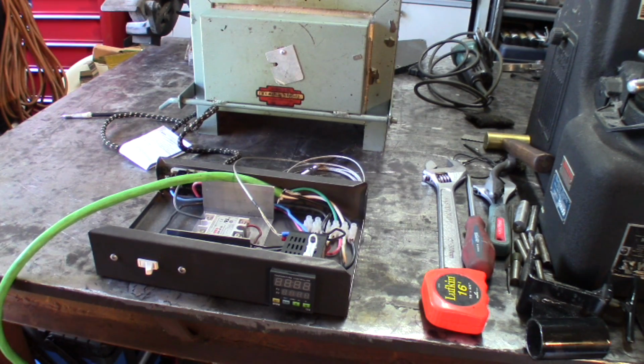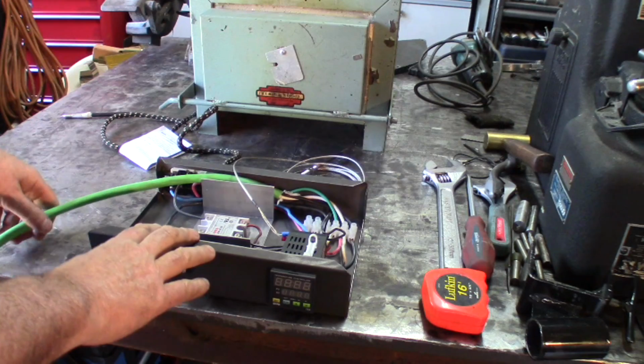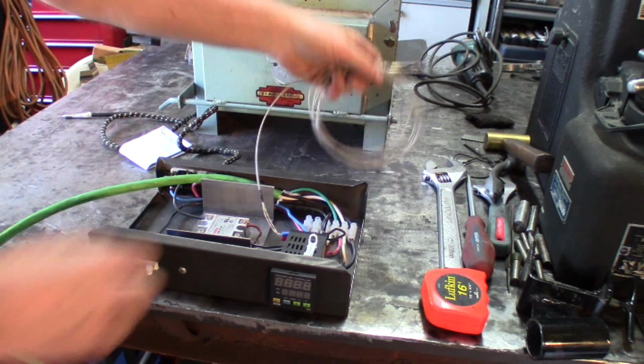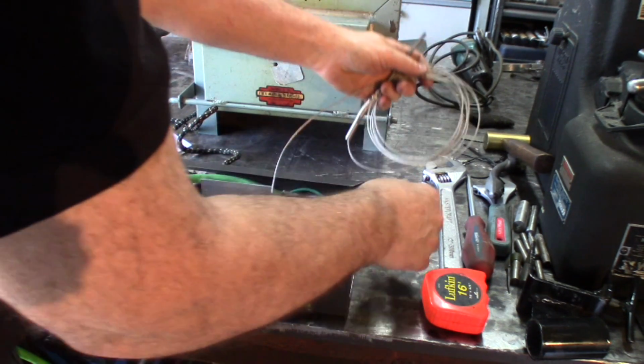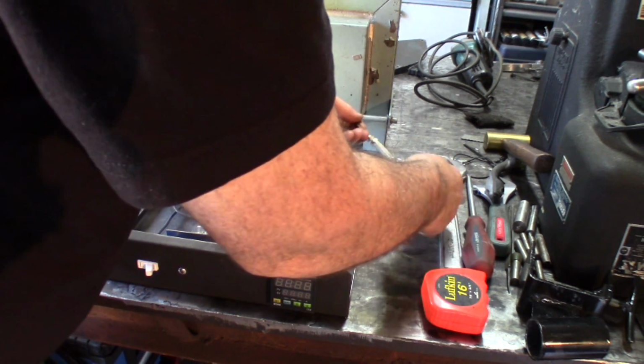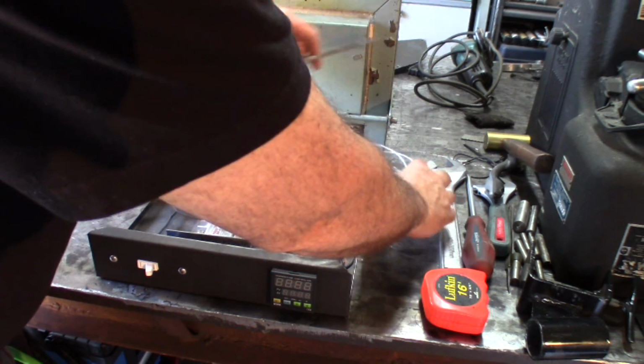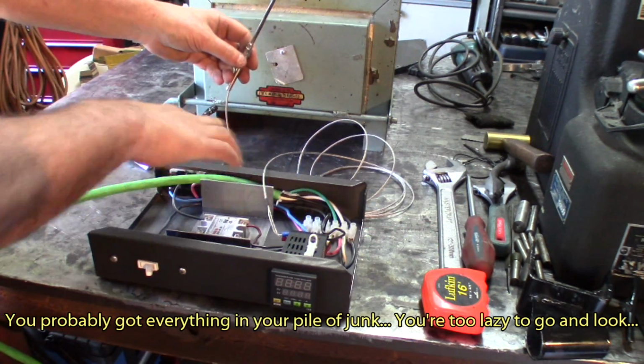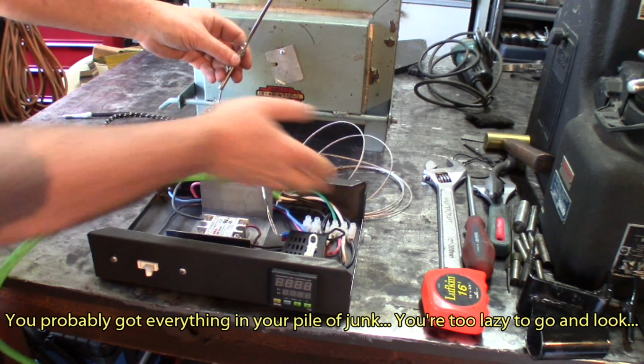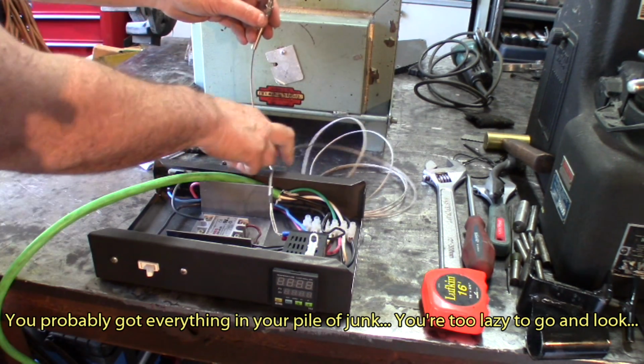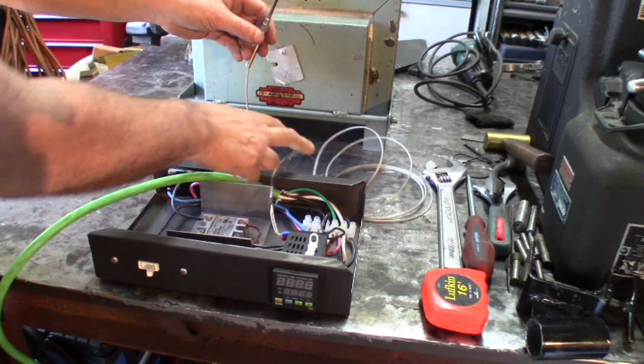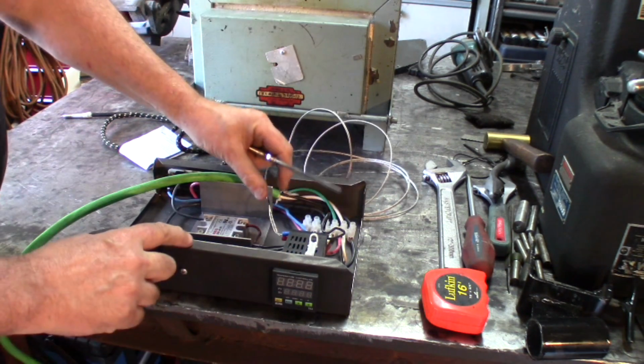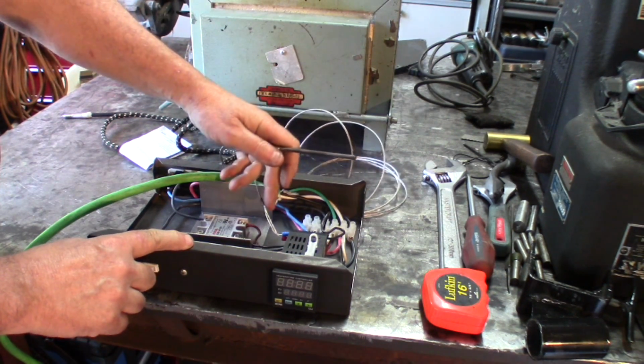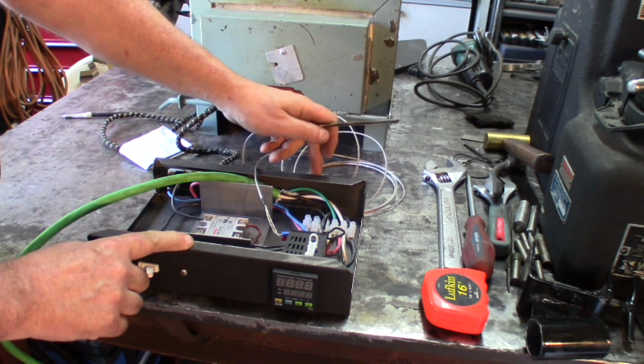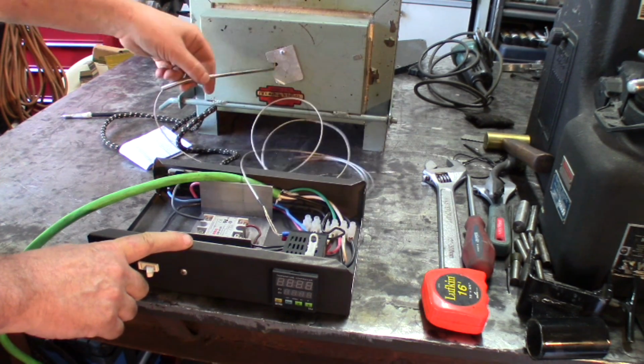Let's put this in, and the probe here, which I have to be careful with, and I'm not exactly set up. I want to get the cable strain relief, which I didn't have time to go fetch, for holding this cable to the back wall there, and I'm going to bring a set of connectors to put the probe, instead of connecting directly to the controller, I'll connect to the back of the case there. But it's coming.